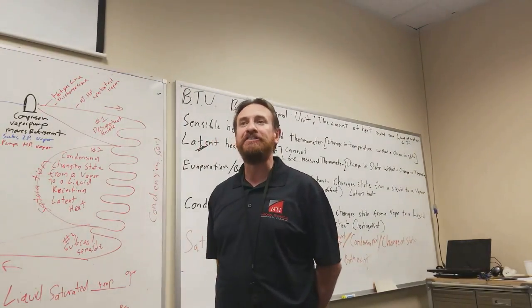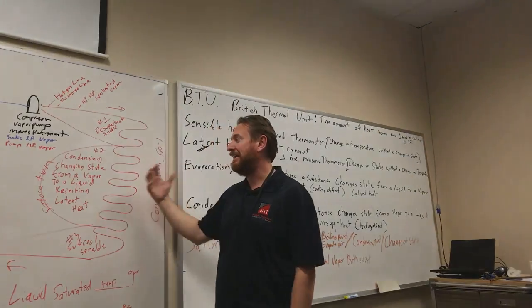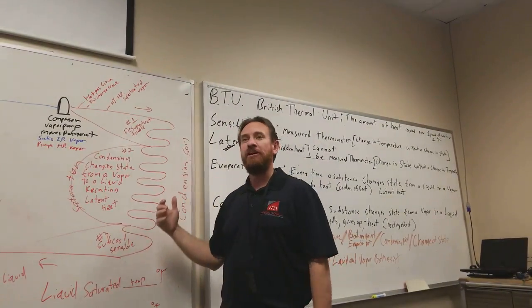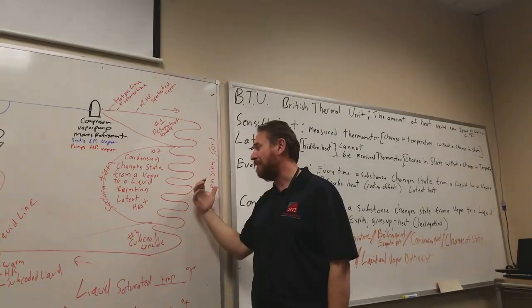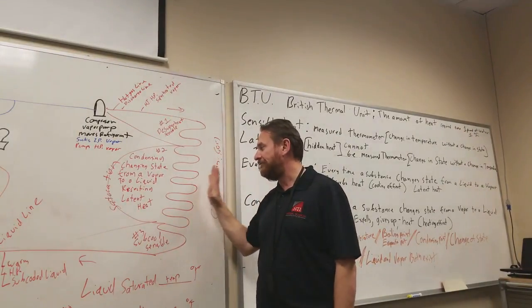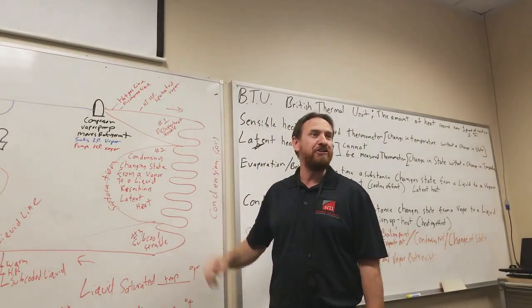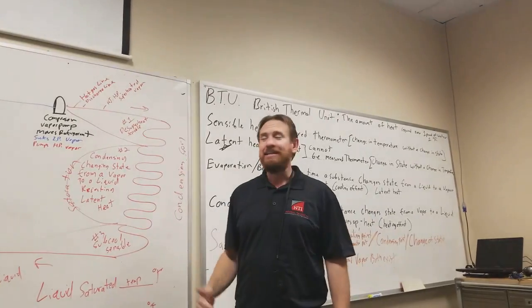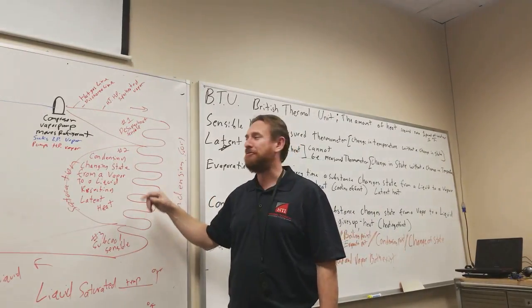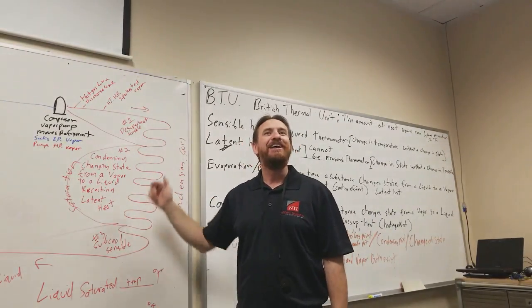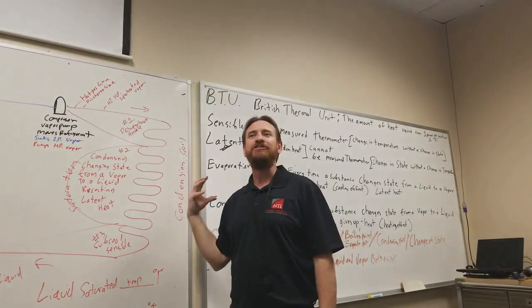As the temperature outside drops, there's less heat acting against it. There's better heat transfer. So as the temperature outside drops, that means there's less temperature affecting this coil. What's going to happen to the pressure on it? It's going to drop. Now, as my pressure drops, what happens to my saturation temperature? It also drops. You see how it's an automatic connection?